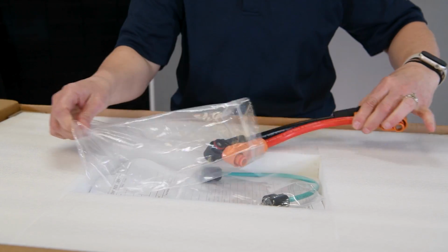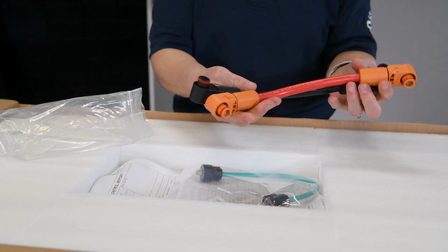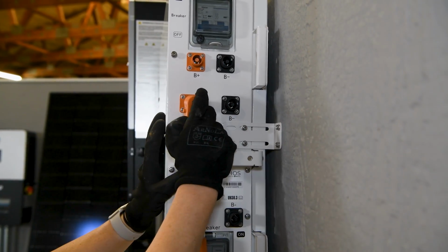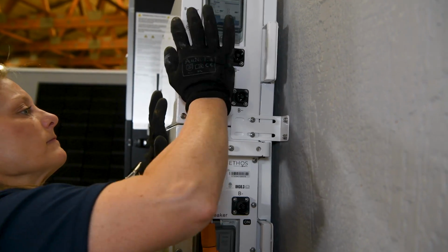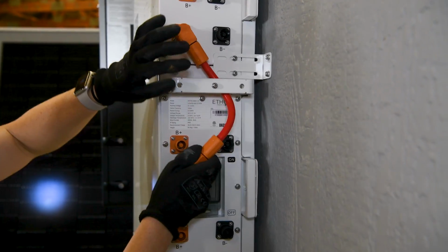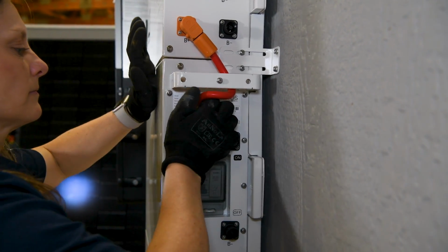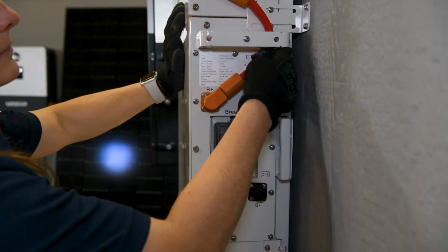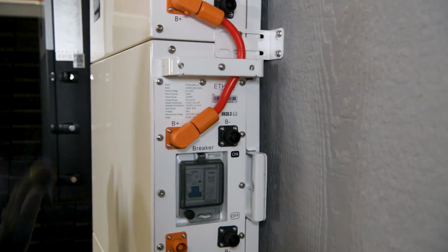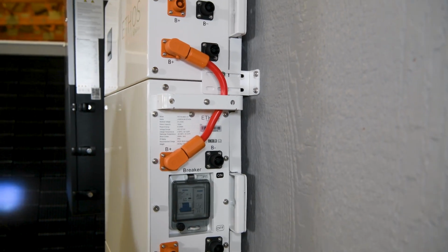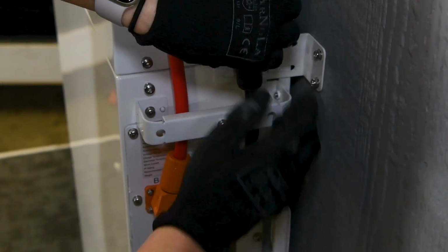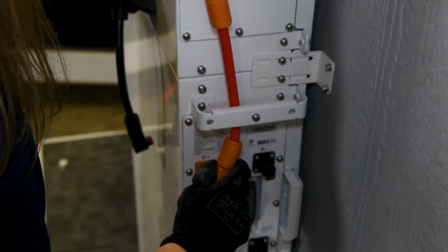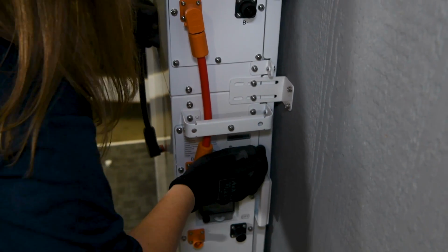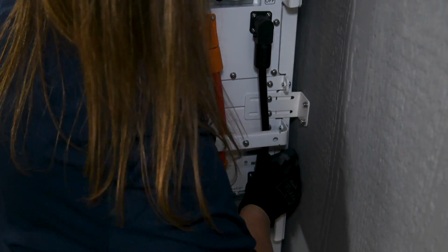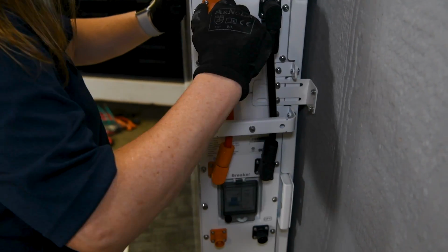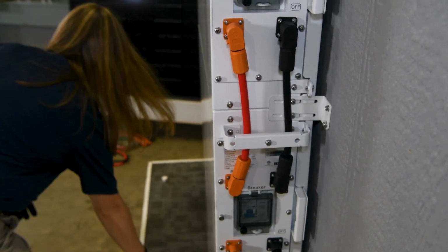Using the 12-inch cables provided in your battery box, initiate the parallel connections from the bottom terminal of the controller box. Connect the cable from this bottom terminal to the top terminal of the first battery module, ensuring positive to positive and negative to negative connections, and carefully route the cable behind the battery handle for a neat setup. Press firmly until you hear a click indicating a secure connection. It's wise to give a gentle tug on the cable to confirm it's properly connected.